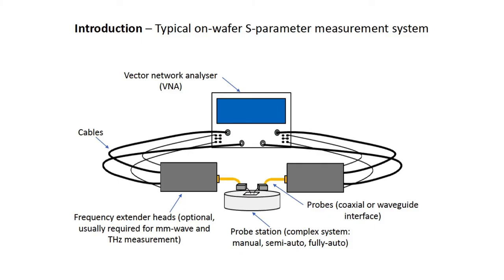I'm sure you're all very familiar with this — this is a typical on-wafer S-parameter measurement system. You have a VNA and cables, and a frequency extender to move our frequency to millimeter-wave and even terahertz. And then you have probes, and you have a probe station.